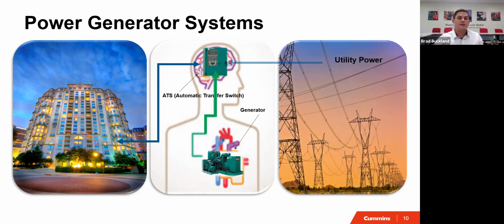If the utility power ends up being lost, it kicks on the generator and flips that over into your main power for the building. So that's how they work together. The ATS isn't always your big ticket item, if you want to say that - it's not as flashy as the generator might be, and in my world that's flashy, I guess. But it's important to note that it is the primary source of some issues that might occur in terms of not having planned maintenance and things like that.